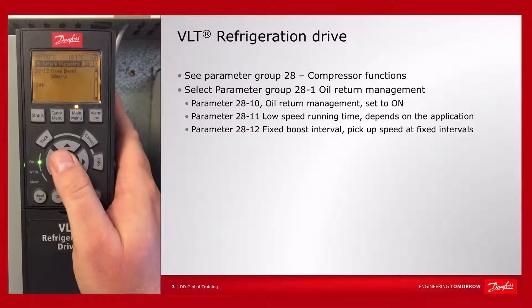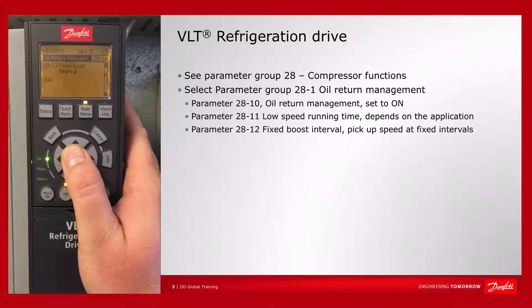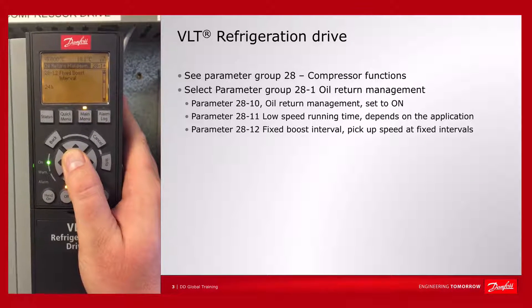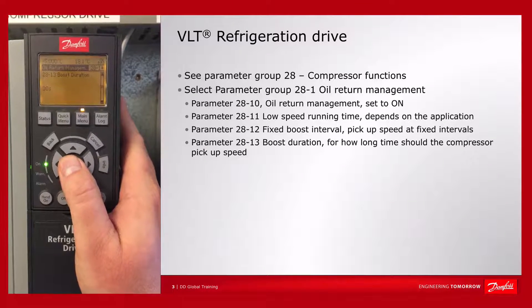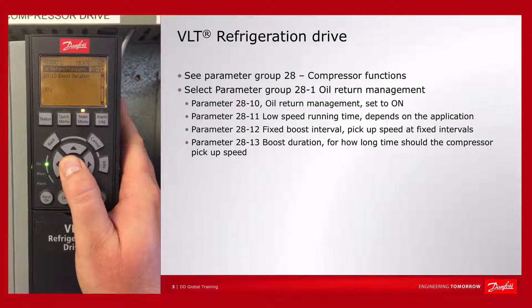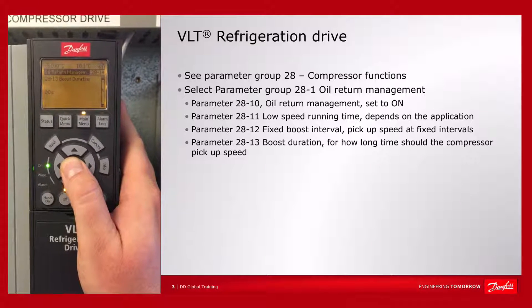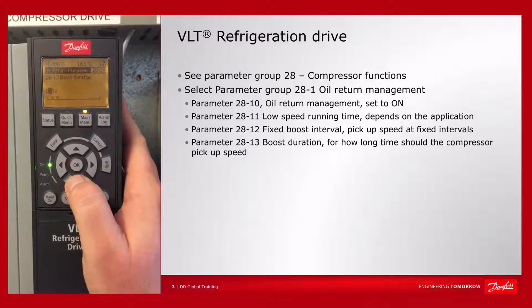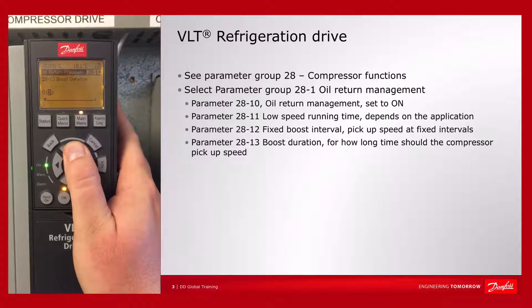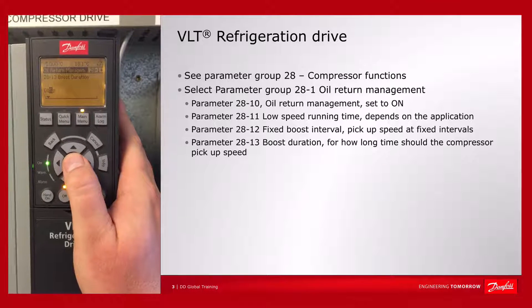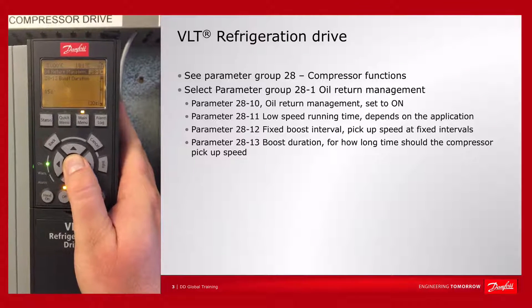Click ok and go to 28.12, where you have the possibility to let the drive pick up speed at fixed intervals — every hour, every 2 hours, 24 hours, or every 2 days. We will leave this as it is and go to 28.13, where you determine the duration of the boost — how long the compressor picks up speed. I will put 15 seconds, though this is system dependent. It could be up to 2 minutes, but in this small system 15 seconds is ok.